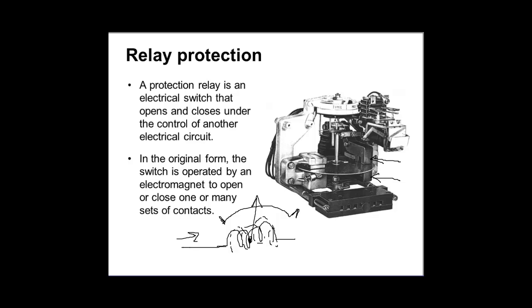It goes back to the setting of the relay. You set it in a way so that even for a small bit of torque, it will start to move, and for a very strong torque, it will start to move. Okay, so is it the current setting of the relay? Yes. Is it correct to say that another name for current setting is the pickup setting of the relay? Yes. So where is that in the relay? Here.